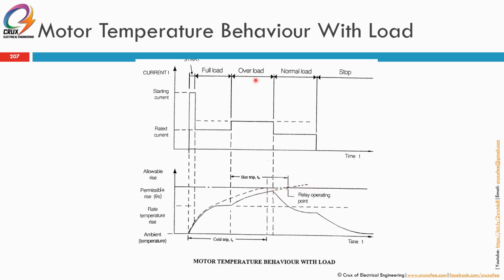But if the overload is removed before it reaches that temperature, it will start to cool down and go back to the normal temperature of the motor under normal load. And finally, once you stop, there'll be some time before the motor finally cools down to the normal ambient temperature. So this cooling time is normally much slower as compared to the heating time of the motor.